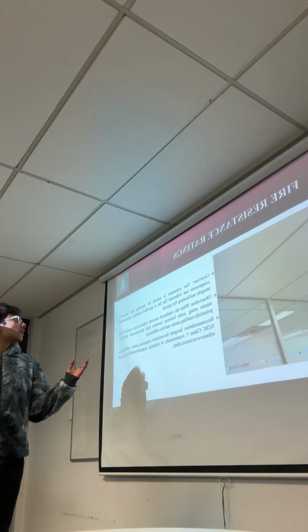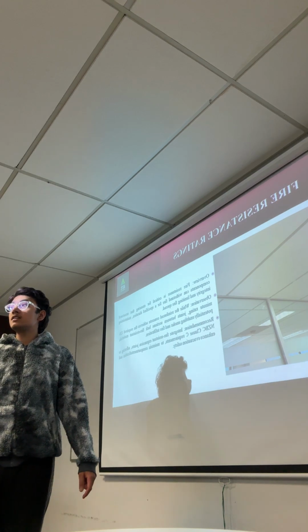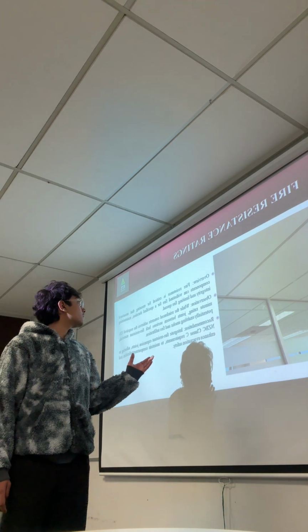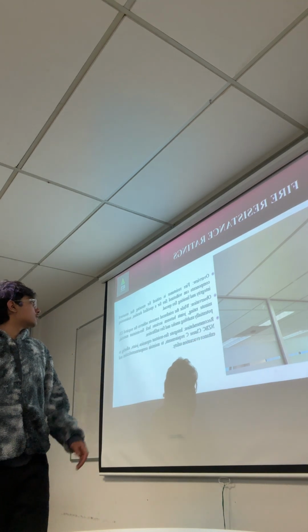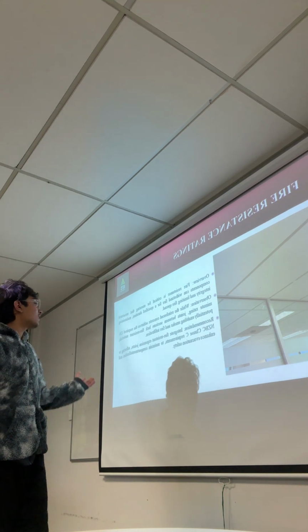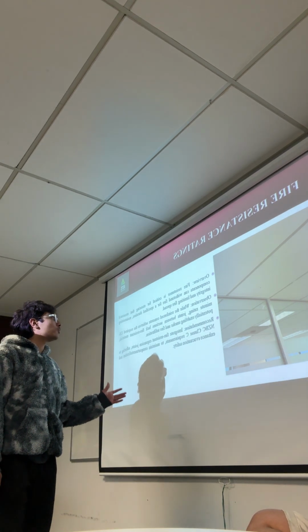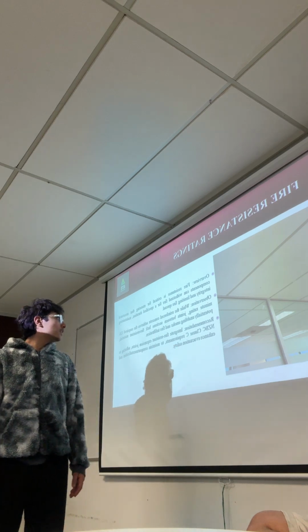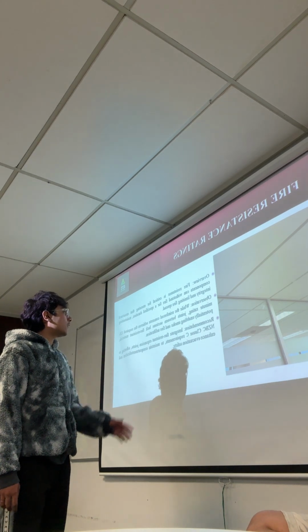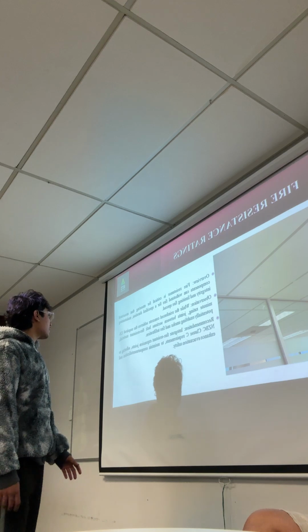So let me explain fire resistance rating. Fire resistance is critical for ensuring the structural components can withstand fire for a specific duration, maintaining integrity and limiting fire spread inside the building. While the reinforced concrete achieves the required rating, for example 120-minute, joints between sections lack fire resistance materials, potentially enabling smoke and fire infiltration. So integrate fire resistance expansion joints adhering to NZBC Clause C requirements to maintain compartmentalization and enhance evacuation safety.